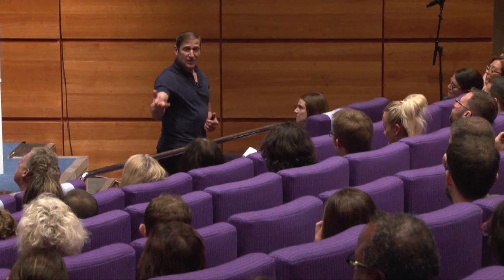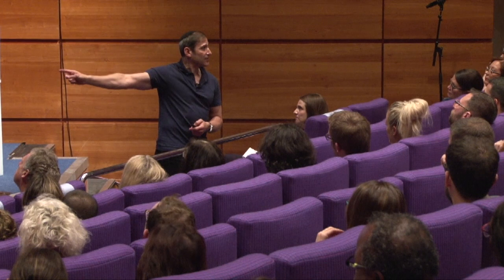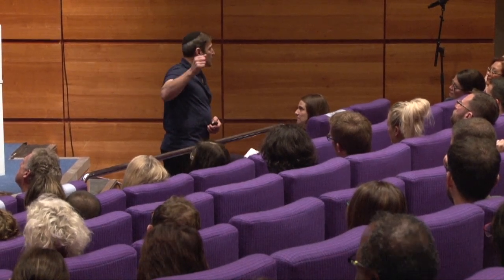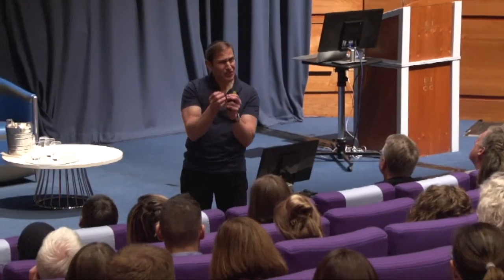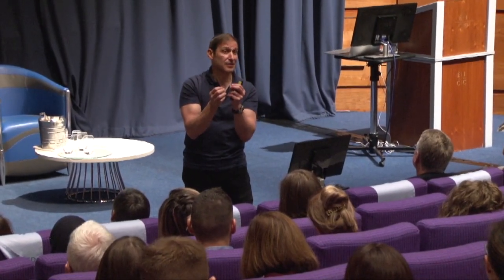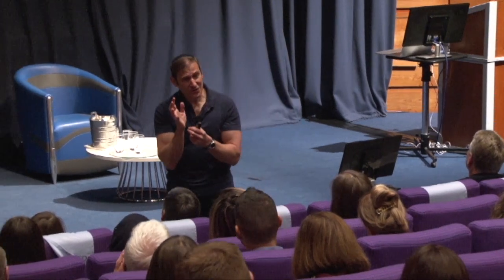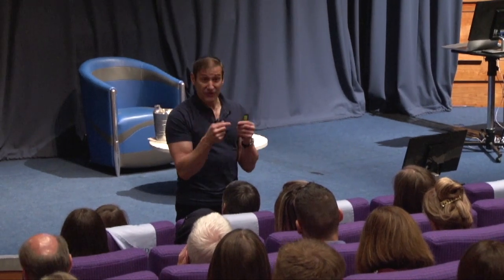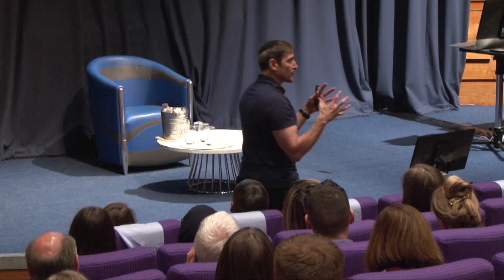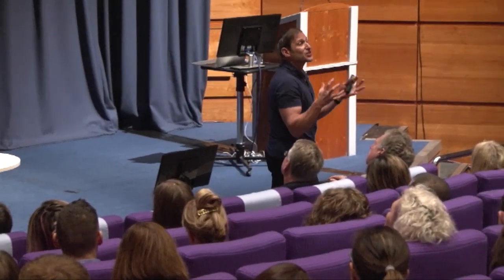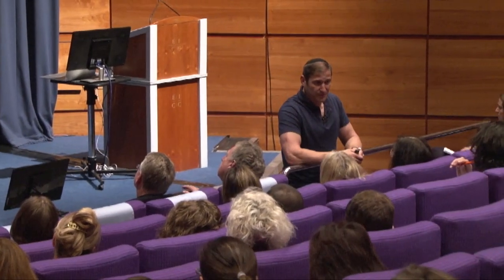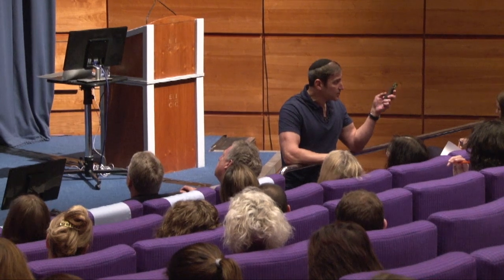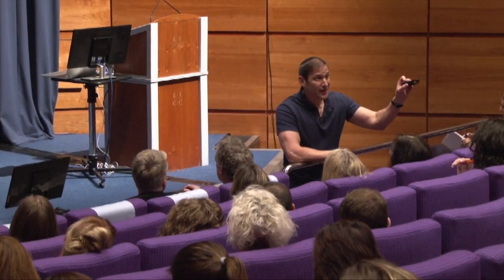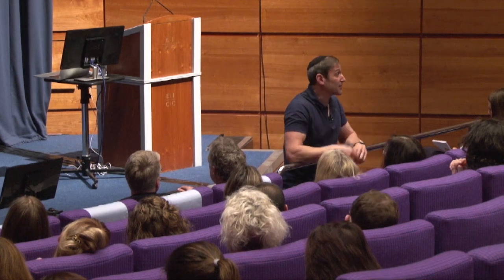And where else? Talk to me. If the whole thing is 3 Tesla, well, the center is 3 Tesla. You pay fantastic amounts of money to have these manufacturers warrant that it's exactly 1.5 or 3 within X number of parts per million. Your written warranty tells you how unbelievably homogeneous it is in the center, about the size of a basketball, a 30 centimeter diameter spherical volume. So in the center, ladies and gentlemen, displacement goes to 0. If you had the wrench in the center of the magnet and let go, I guarantee it drops to the floor. It doesn't even know there's a magnetic field around.